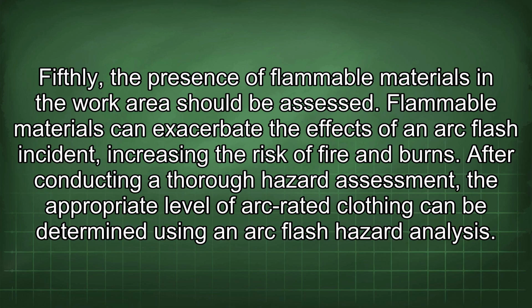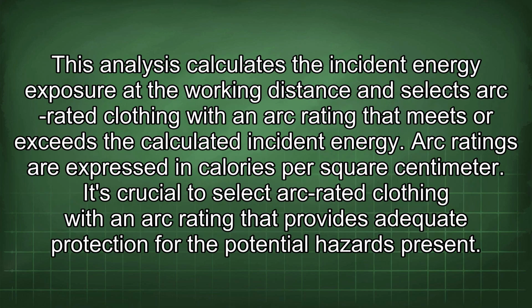After conducting a thorough hazard assessment, the appropriate level of arc-rated clothing can be determined using an arc flash hazard analysis. This analysis calculates the incident energy exposure at the working distance and selects arc-rated clothing with an arc rating that meets or exceeds the calculated incident energy. Arc ratings are expressed in calories per square centimeter. It's crucial to select arc-rated clothing with an arc rating that provides adequate protection for the potential hazards present.